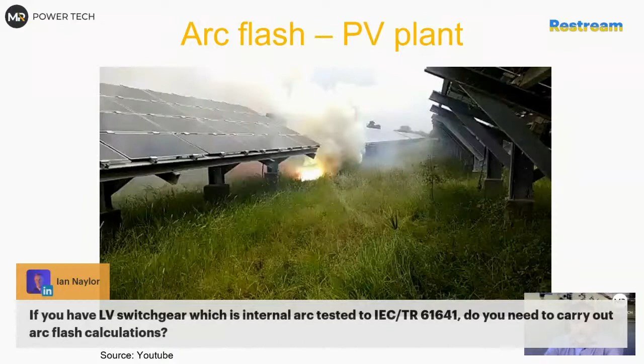And people think that they can walk across or stand in front of the switchgear like this, doing some switching, or maybe something is wrong, but they are standing there because it is arc rated and it's supposed to be safe. And they might wear something like this plastic clothes, I can call it, like polyethylene or whatever, and this thing will ignite. That's the conclusion from the test, that this is not cotton, so you have to wear something more than cotton still walking around the arc rated switchgear. Otherwise, if you wear something different, you might ignite as well and get burned.